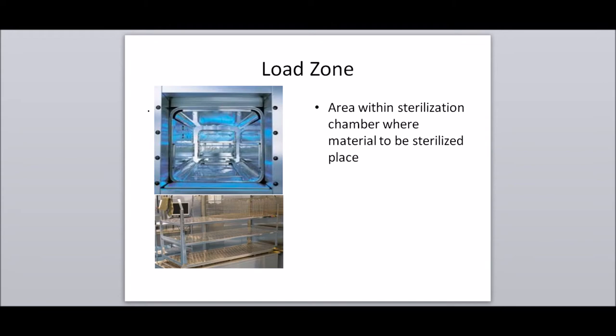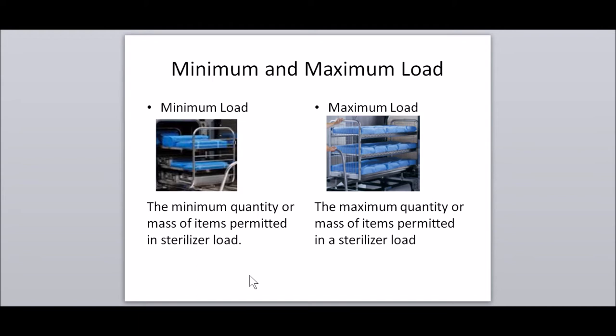Load zone: the area within a sterilization chamber where material to be sterilized is placed. Generally it is a carriage. Minimum load: the minimum quantity or mass of items permitted in a sterilizer load. Maximum load: the maximum quantity or mass of items permitted. For example, the minimum load may have 4 boxes and the maximum load 15 boxes.